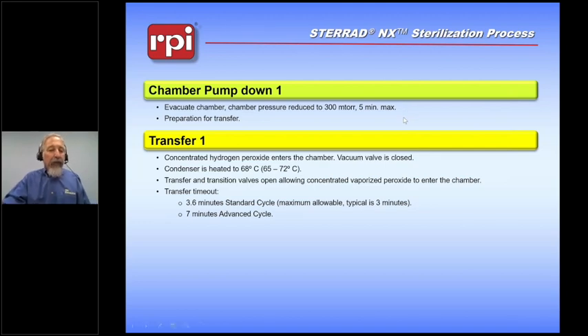We look at the hydrogen peroxide through the monitoring system. If it does not show up within 3.6 minutes in the standard cycle, that'll cause a transfer timeout, or 7 minutes within the advanced cycle. The advanced cycles are longer and allow the machine to move the materials at a better, more leisurely pace.